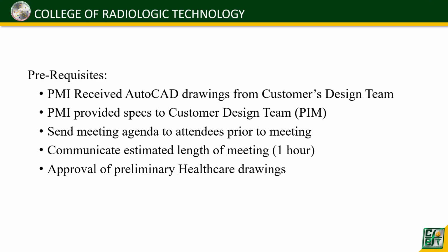So during the first meeting, ito yung mga required prerequisite or kailangan i-present sa meeting. Okay? So yung AutoCAD drawings ng coming from the customer's design team, kung ano yung design ng radiology department na gusto ng hospital admin. And the PMI provide specs to the customer's design team. Okay. Specs. Ano yung specs? Yung mga kinakailangan na, let's say sukat.